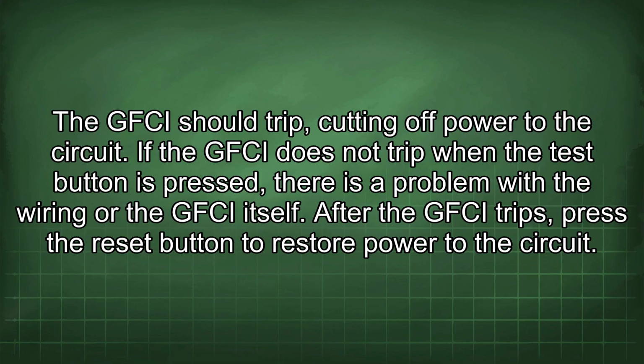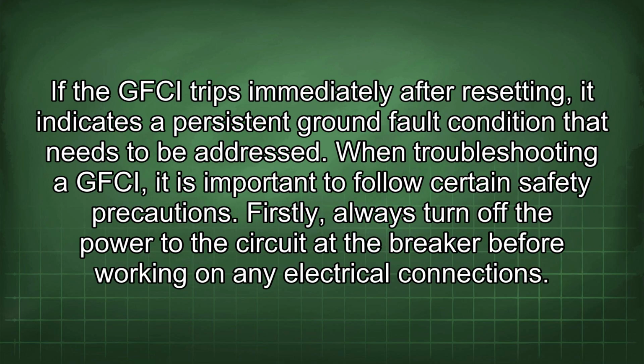If the GFCI does not trip when the test button is pressed, there is a problem with the wiring or the GFCI itself. After the GFCI trips, press the reset button to restore power to the circuit. If the GFCI trips immediately after resetting, it indicates a persistent ground fault condition that needs to be addressed.